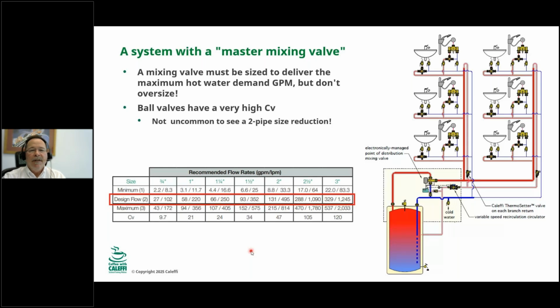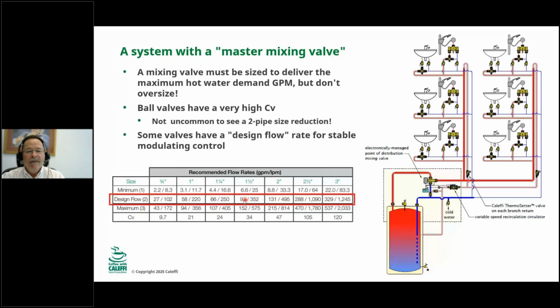Okay, we talked about the design flow rate. So for example, this red box here, the design flow, this is the Caleffi product, and this is the GPM at 7.5 PSID pressure drop across the valve, which is a really good pressure drop for a modulating ball valve, and that works for ours. Now the valve will handle up to what we call this maximum here, and we rate ours at 20 PSID. So the valve will deliver more than that, but that's going to be an unusual condition. The sweet spot for sizing is our design flow rates.